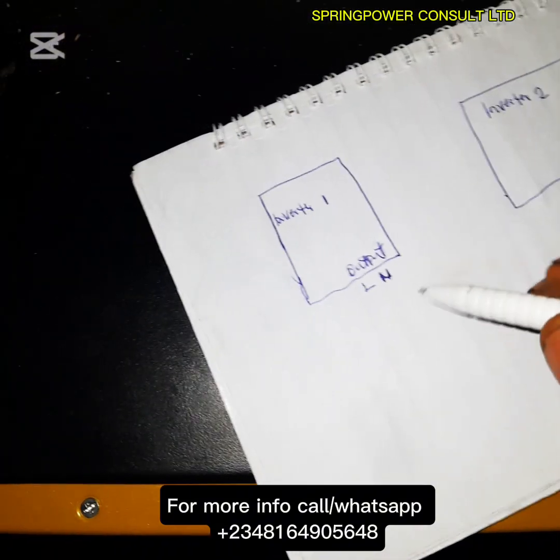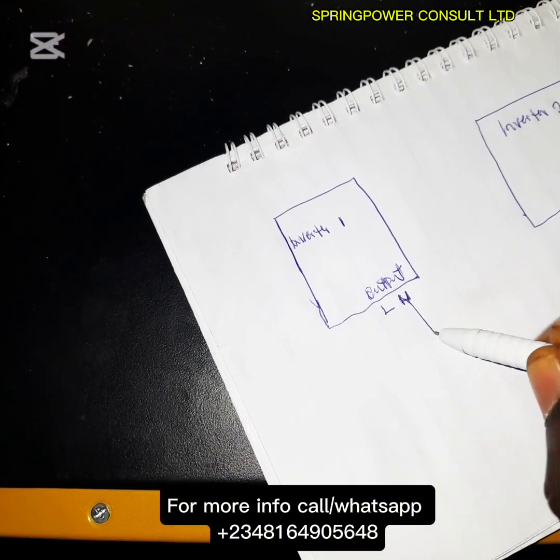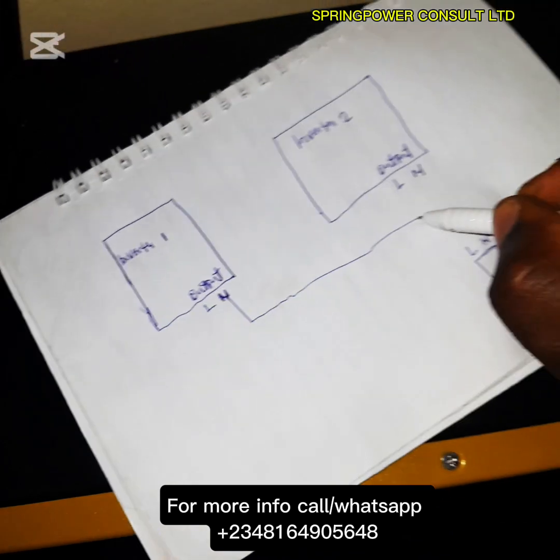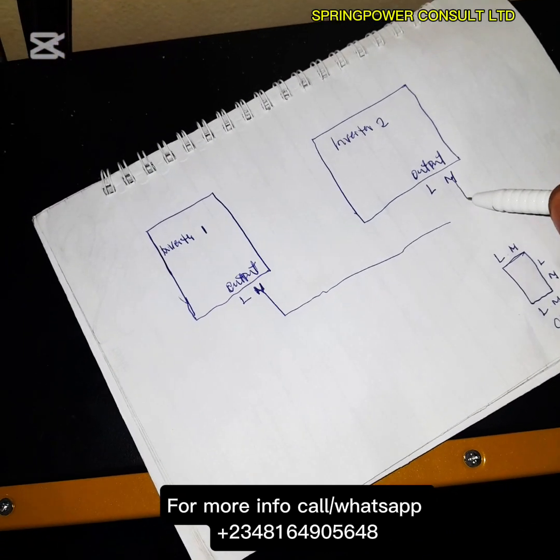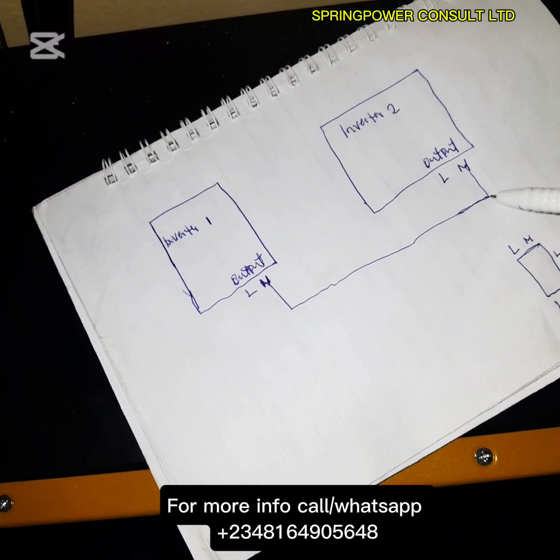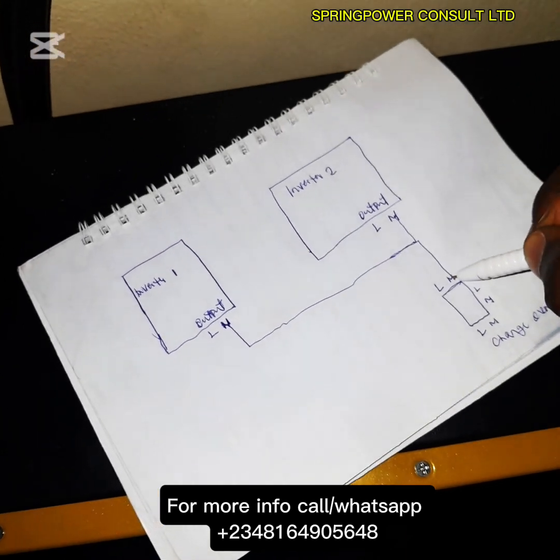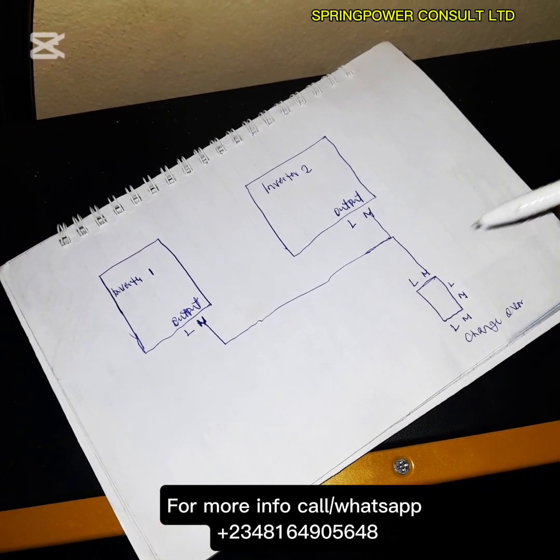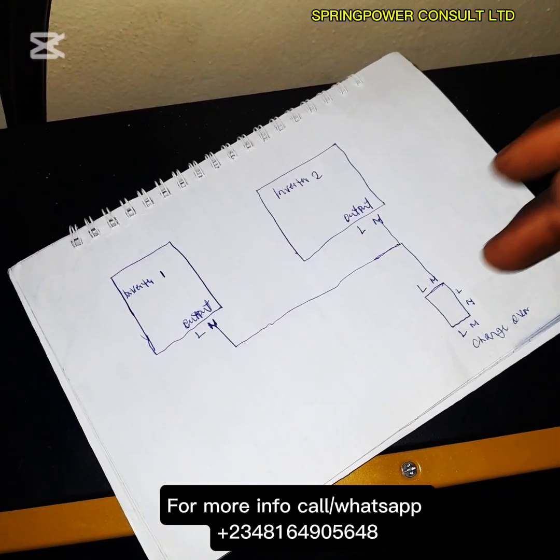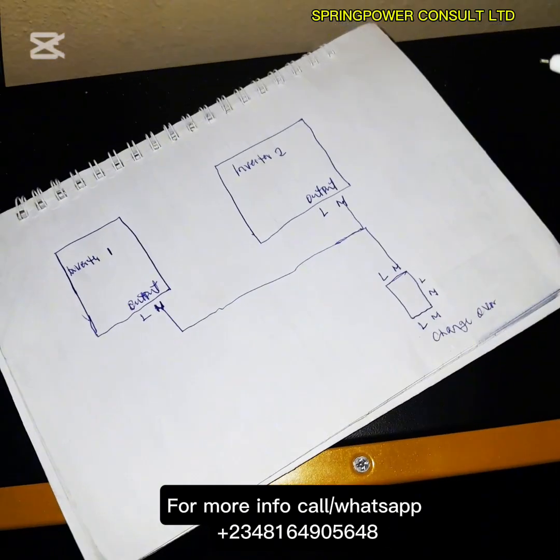The way to go about it: connect the neutral of inverter 1 in parallel to the neutral of inverter 2. Then connect it straight to either your output changeover or your output circuit breaker, then to the changeover, whichever way you do your connection.